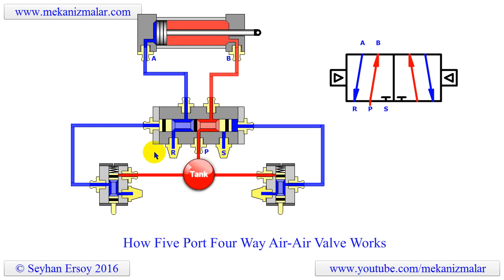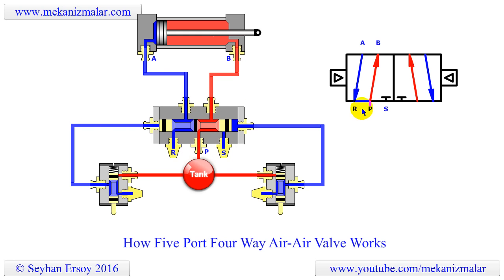It is a 5-port, 4-way, air-to-air operated valve. It is called this because there are 5 ports that can be used to make connections. The valve shown here has 1 port connected to the pressure source, 2 ports connected to the cylinder, and 2 ports reserved for exhaust. These ports are named as follows: Port P is connected to the pressure source, ports A and B are connected to the air cylinder, and finally R and S ports are connected to the atmosphere. The connections are also shown on the valve symbol on the right.